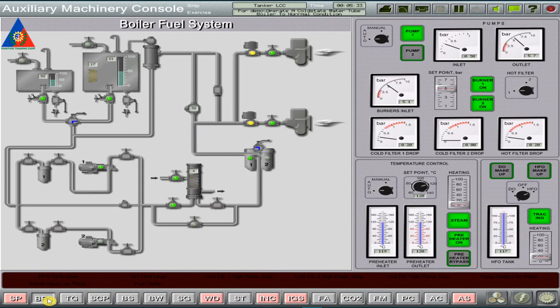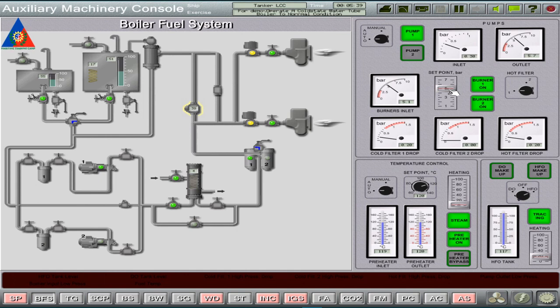Here we increase the boiler fuel feed pump pressure setting to 7 bars to fast track steam pressure production on the boiler.